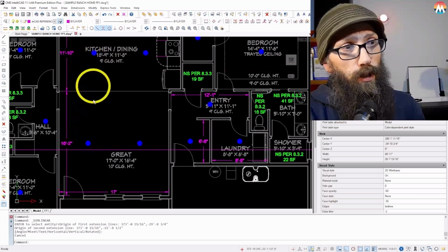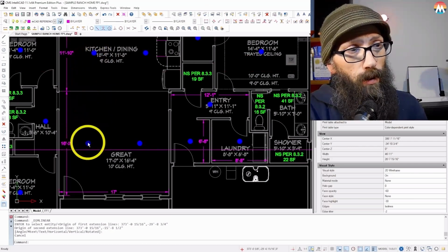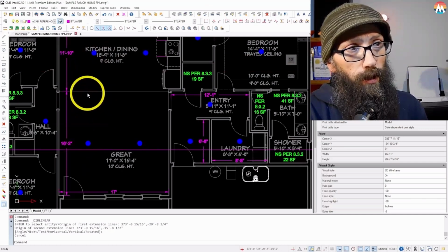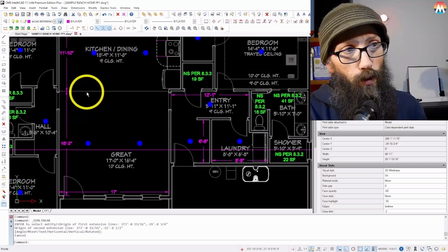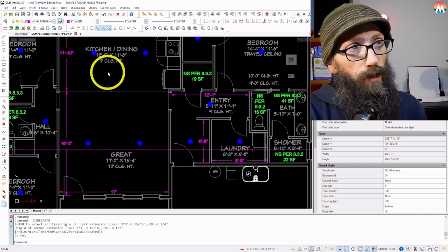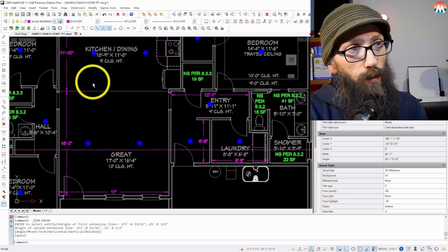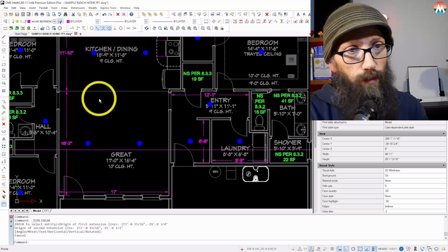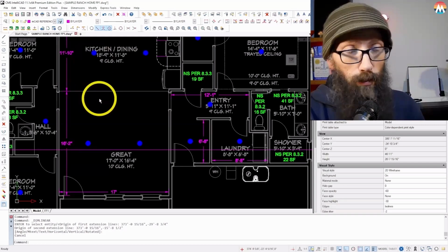Where this sprinkler stops, right out here, 2 inches before the edge, this ceiling is higher, and where this is sitting, it's lower. And so this is going to spray out 8 feet this direction. And it's not going to be a problem. We got plenty of coverage.